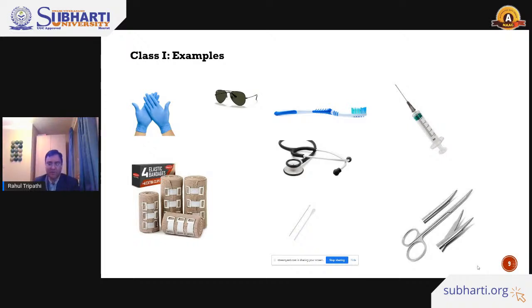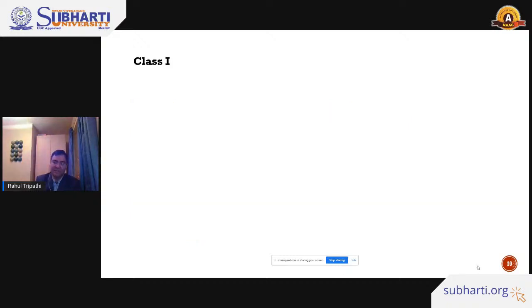If it's general use for the cleaning of earbuds or something else, that is not to be considered as a medical device. But if you are applying pharmaceutical products, or using cotton buds for the testing purposes, for the diagnostic, that needs to be registered under the medical device. The same goes with the syringes, the toothbrushes and the sunglasses. They are simple equipment, but they serve some medical or diagnostic purposes. That's why it falls under the medical device.